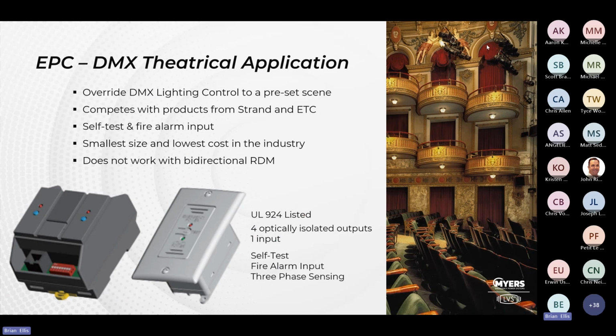EPC DMX. Okay, so this is a unique device. There's really only 3 manufacturers that make something similar, Strand and ETC. Ours is about half the cost, but really it comes with 2 devices. One is the DMX bypass. So you have 1 input and 4 outputs of DMX. You pass the DMX through, you use whatever DMX system you're providing, the console, the theatrical, whatever it is, and then you would set up a scene, a look, so that when you lose utility, it would recall that scene. So this device is DIN rail mounted. RJ45 connects to this 3-phase loss device. So again, small footprint, really good looking small device.